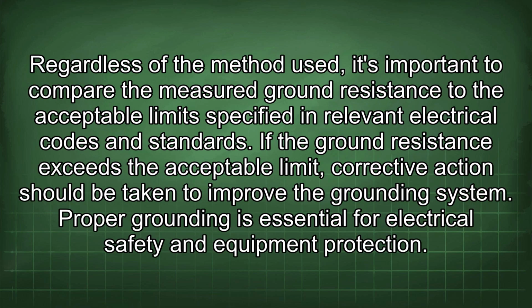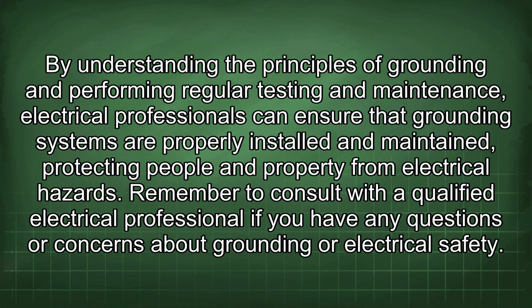Regardless of the method used, it's important to compare the measured ground resistance to the acceptable limits specified in relevant electrical codes and standards. If the ground resistance exceeds the acceptable limit, corrective action should be taken to improve the grounding system. Proper grounding is essential for electrical safety and equipment protection. By understanding the principles of grounding and performing regular testing and maintenance, electrical professionals can ensure that grounding systems are properly installed and maintained, protecting people and property from electrical hazards. Remember to consult with a qualified electrical professional if you have any questions or concerns about grounding or electrical safety.